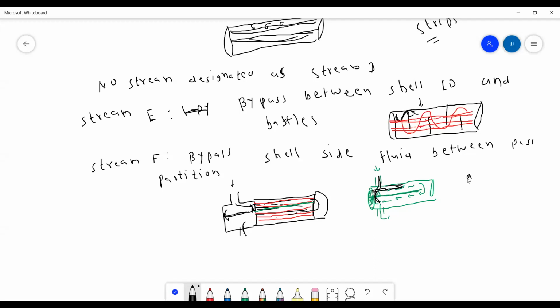But due to the gap, as already I mentioned, the gap between the tube sheet and pass partition plate, the fluid directly bypasses. So this shell side fluid cannot come into contact with the tubes so that heat transfer takes place. So in this condition also, the heat transfer coefficient is reduced.